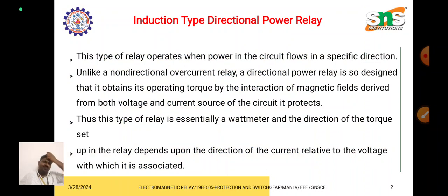This type of relay operates when the power in the circuit flows in a specific direction. So it is a directional relay. If the fault current flows in a particular direction, the relay will operate, either forward or reverse, but not both. If it is non-directional, the fault current may go in any direction, so the relay will identify it and operate. But with the directional relay, if a fault occurs, the current will flow through the specified direction, so that only the directional relay comes to operate.